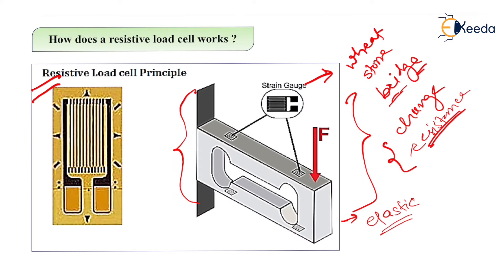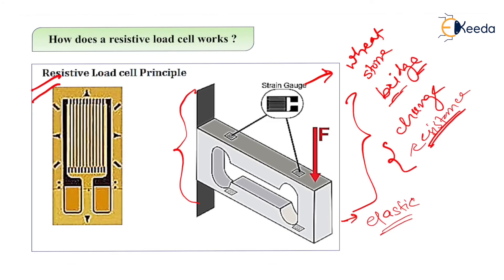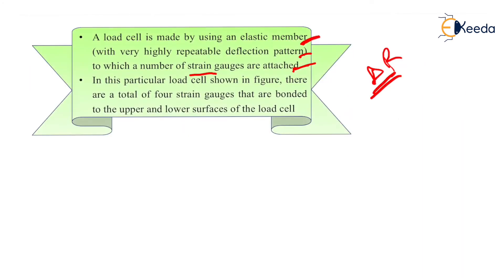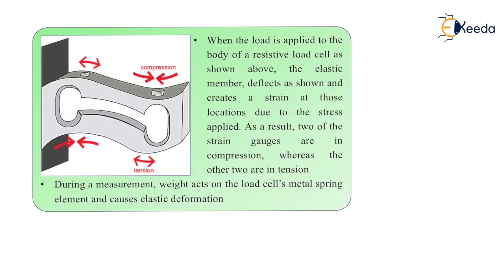When force is applied to the load cell, it deflects the resistive load cell to which strain gauges are attached. In this particular load cell, there are a total of four strain gauges bonded to the upper and lower surfaces. These four strain gauges are responsible for giving us the change in resistance. When the force is applied, deformation takes place in the load cell.